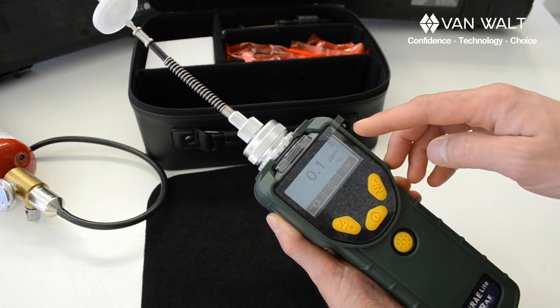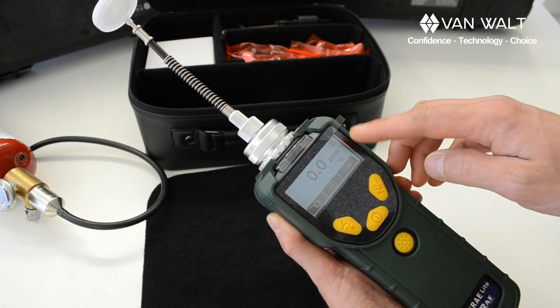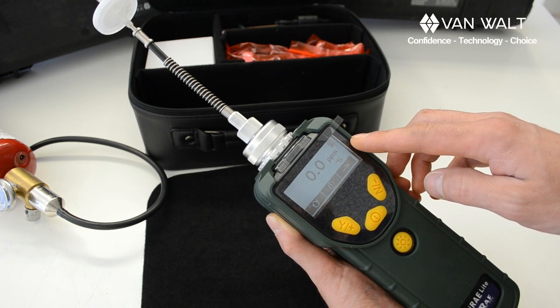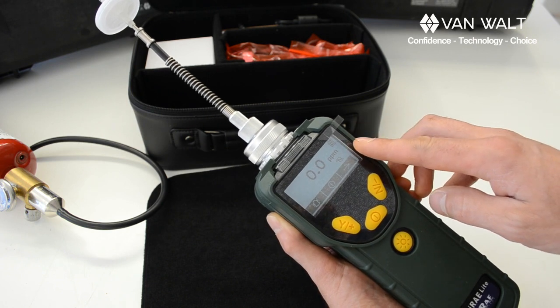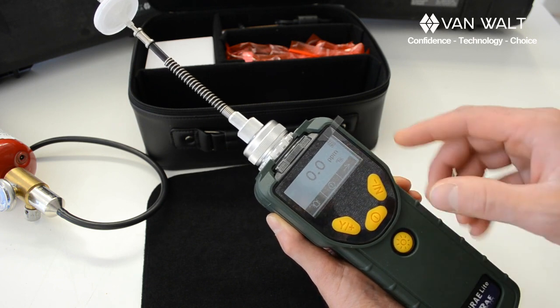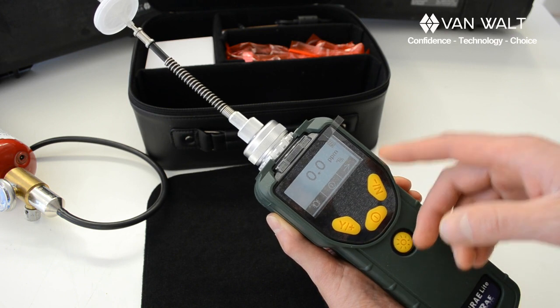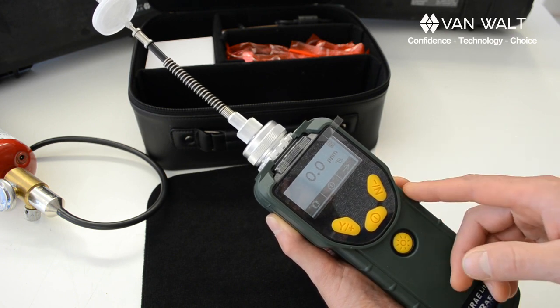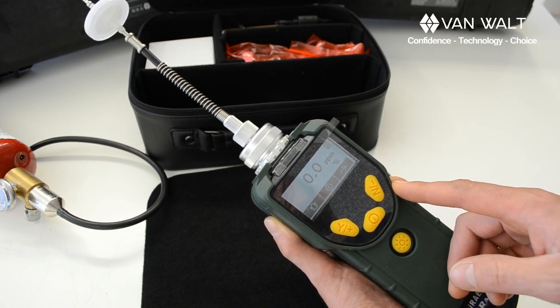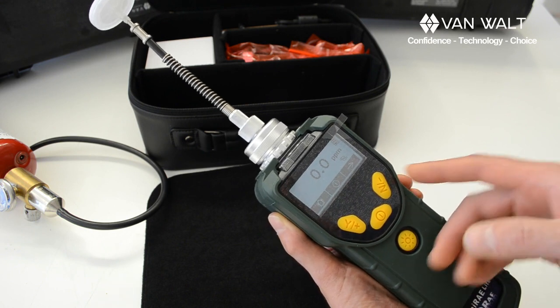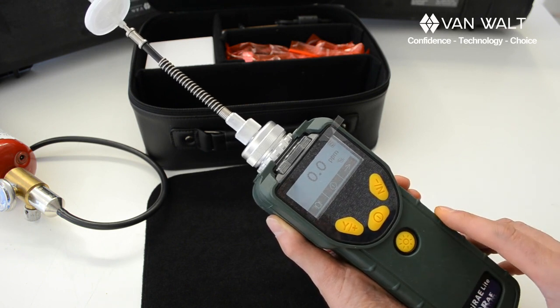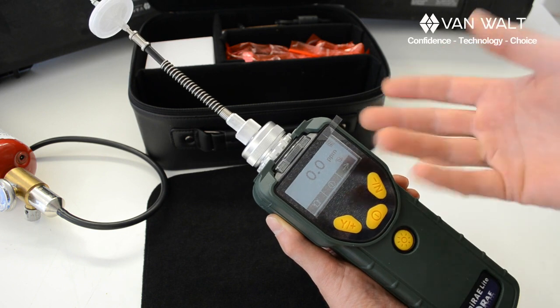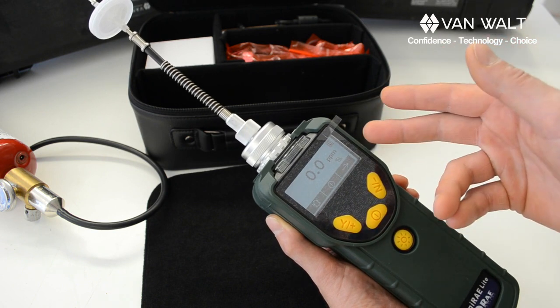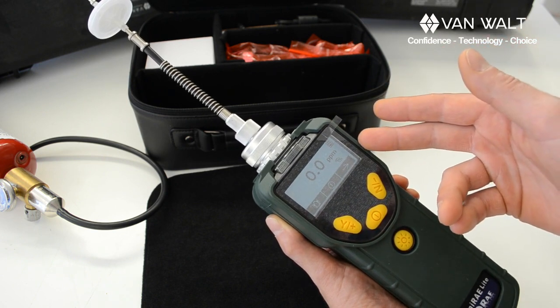It's displaying in parts per million and as if isobutylene, and that is the gas that it's calibrated to. There is no function on this machine for adjusting for response factors, so that is something that you will have to do manually, but it also keeps things very simple. You always know where you're at, and so that is one good feature to view it like that.